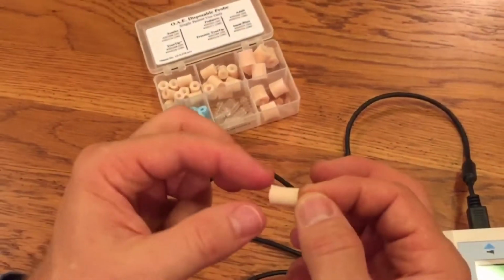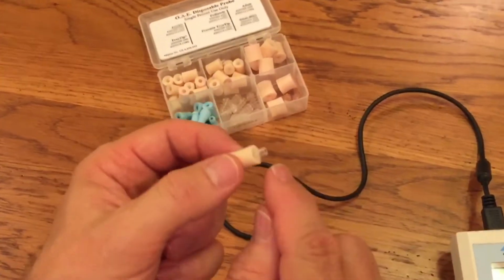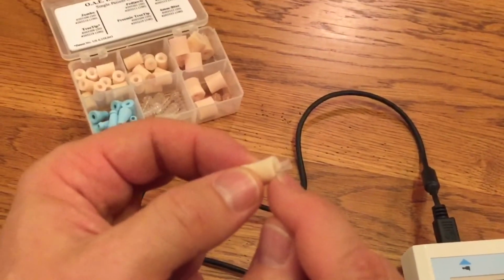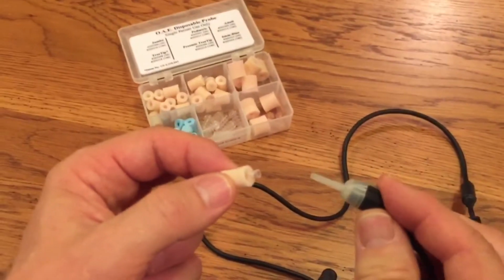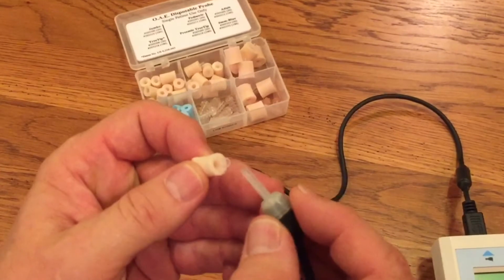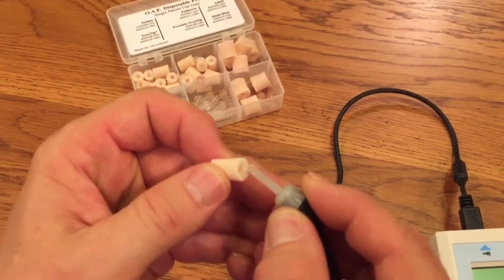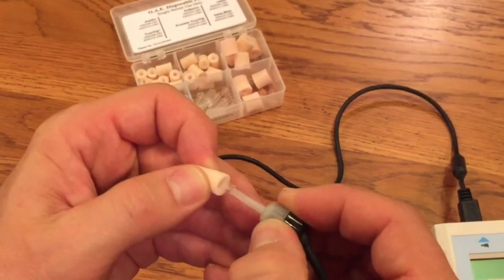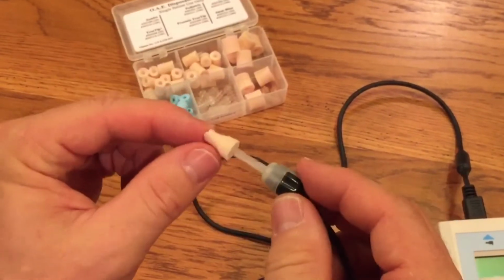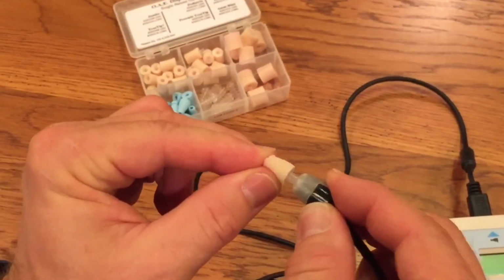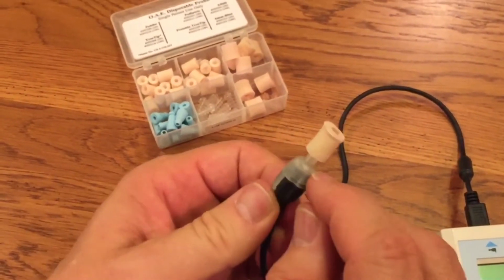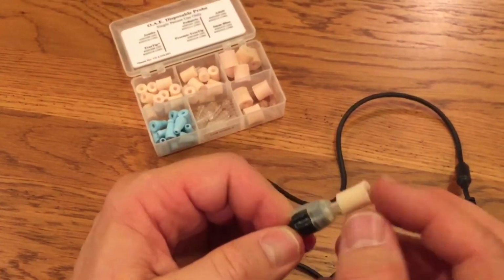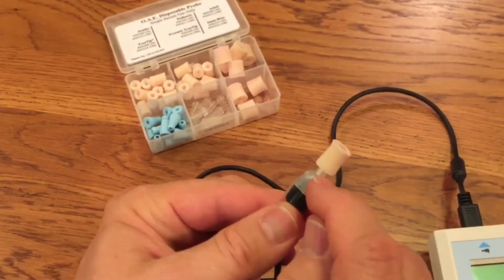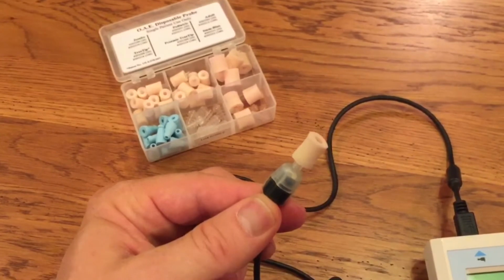Now you'll need to take your probe cover and make sure that the plastic portion is facing towards the probe. That's the part that goes on first. Then you will fit the plastic over the end of the nozzle of the probe, and push it all the way down to the base. It needs to fit all the way down to the base. It's calibrated to fit firmly all the way on.